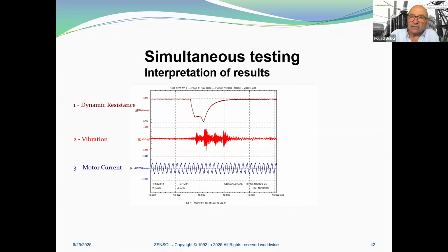As can be observed, the accelerometer signature is characterized by 4 main peaks, and the first two correspond to a specific value of current. With this, we used high-speed video for the first time, and these first two peaks have been identified as follows. The first is the impact of the first auxiliary contact entering the new tap position, and the second is the impact of the main contact entering the new tap position. The two final impacts are not related to the main contacts of the switching taps.